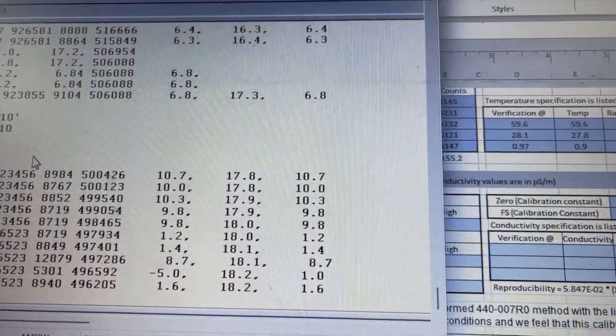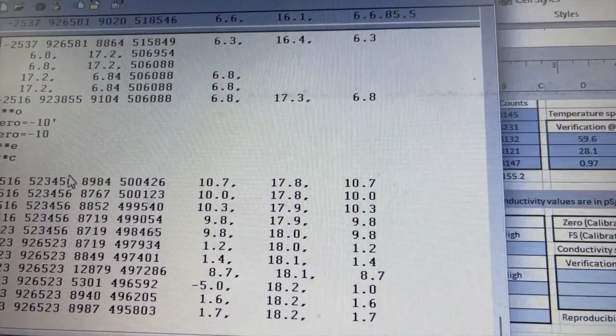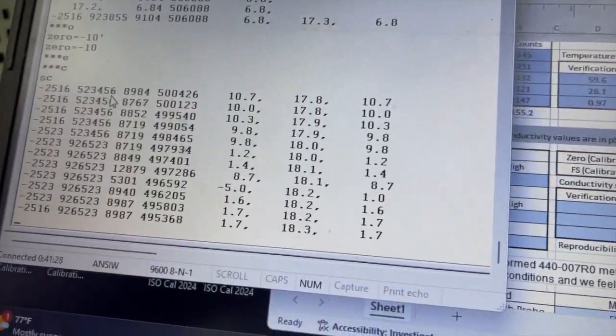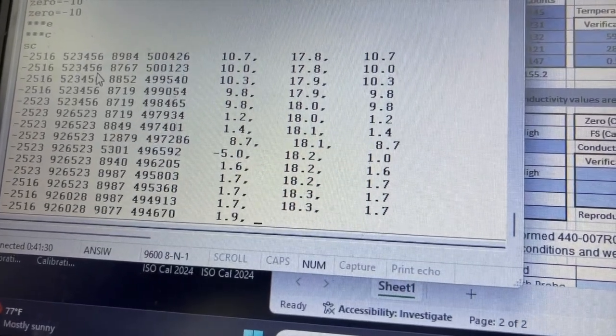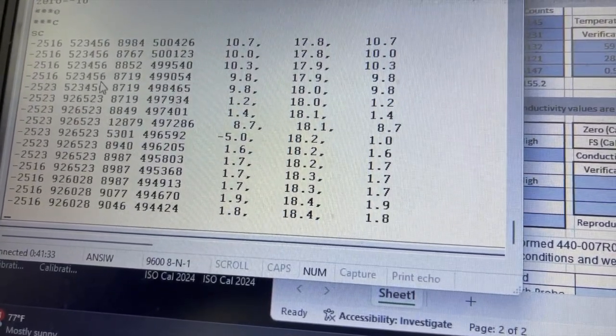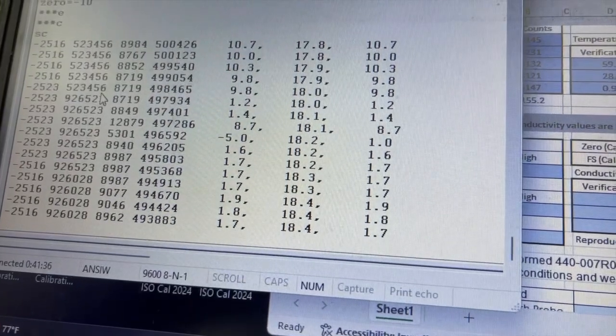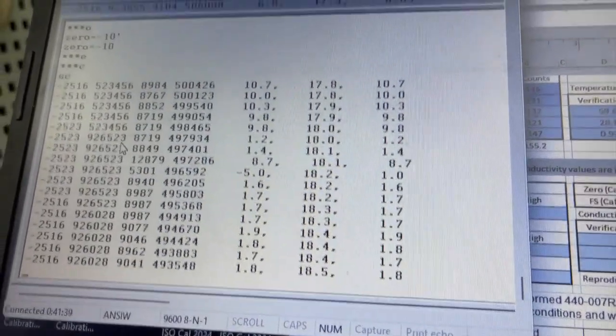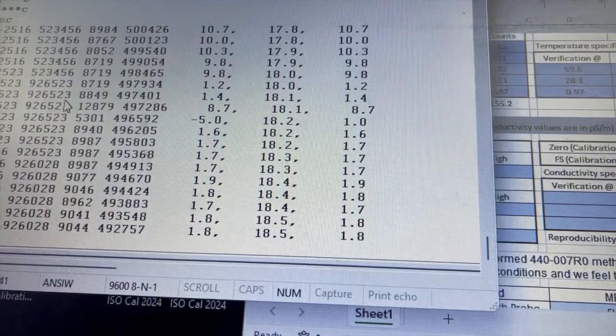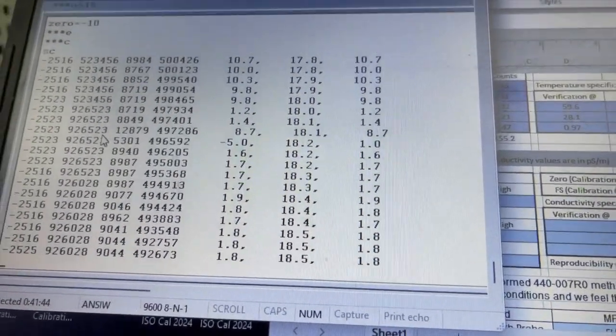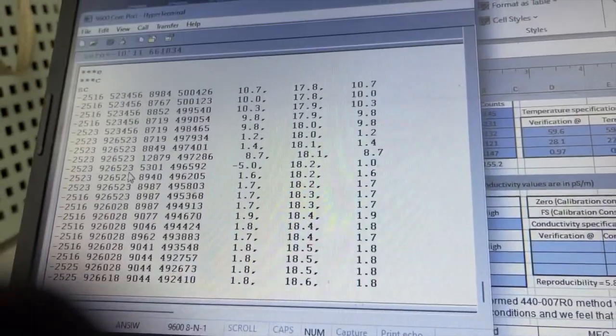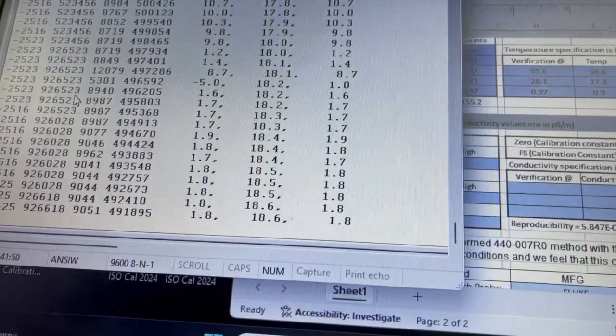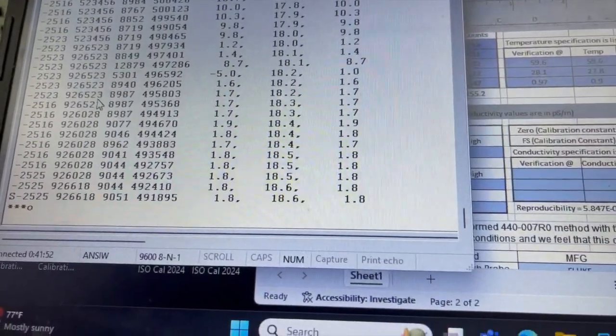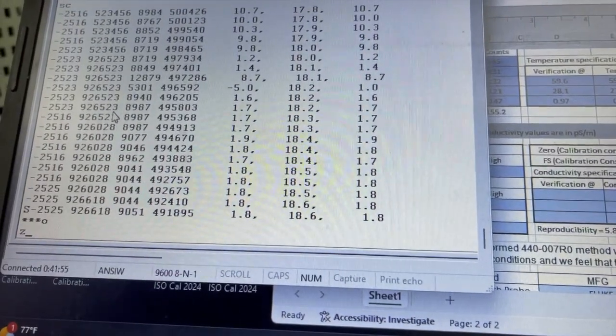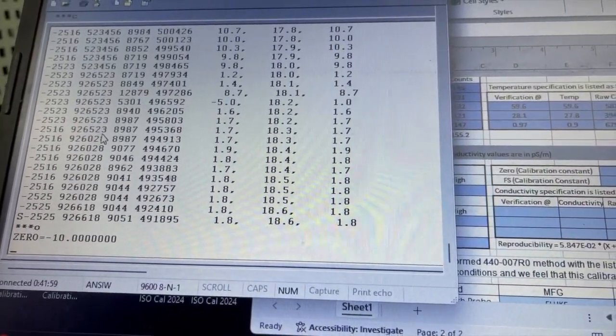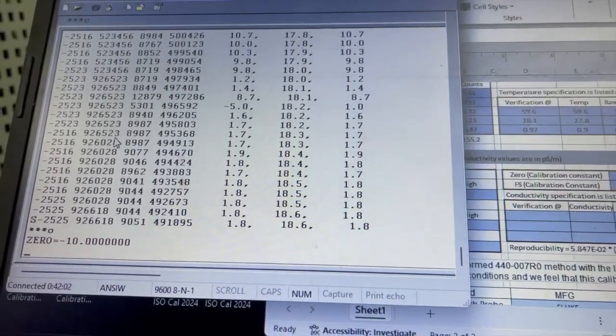So we have a reference of 0.9, and when we run our inline sensor in calibration mode, so you go open mode, calibration mode, we are at 1.8, 1.7, so we need to adjust our sensor down about 0.9 in order to get the value that we want. So to do that, hit stop. We'll check what our 0 is. We want to go down about 0.9 to get where we want.